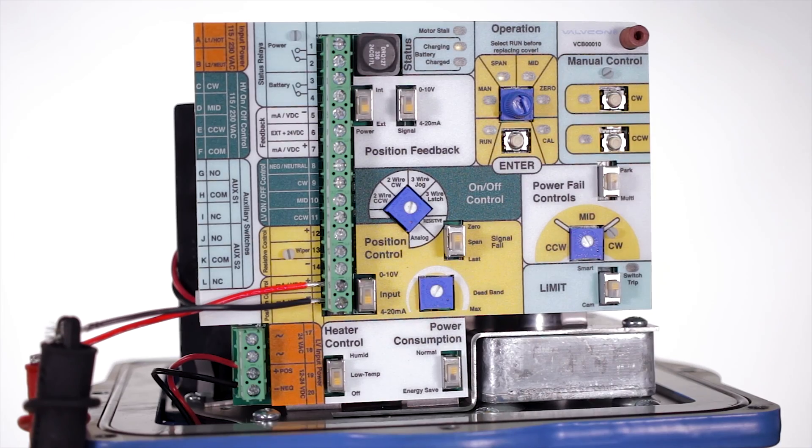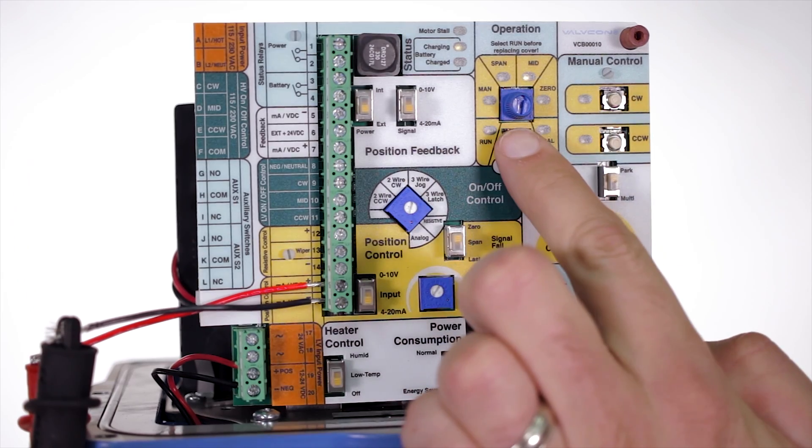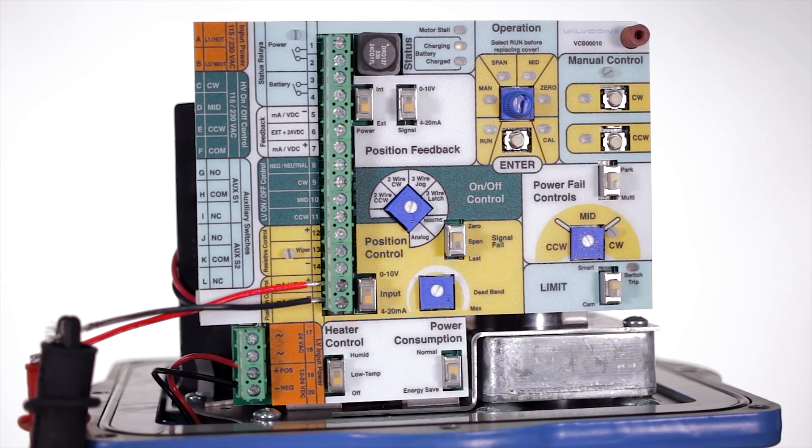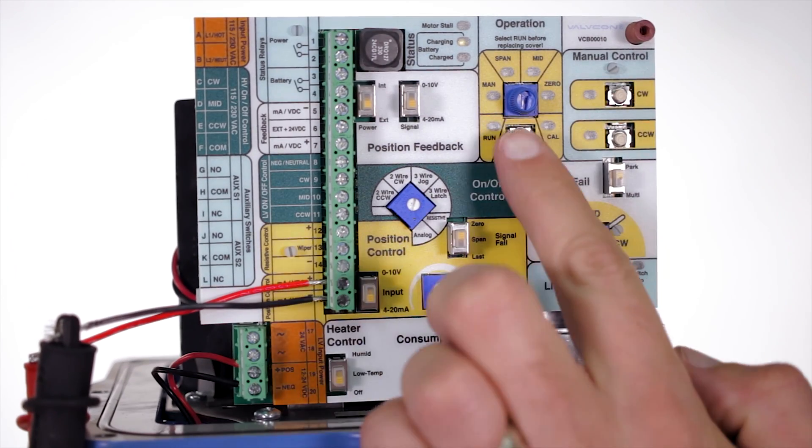If you want the actuator to have a different fail position than fully open or fully closed, turn the operation mode switch to mid, hold enter until it flashes, then set the valve to the desired position and press enter to lock it in.